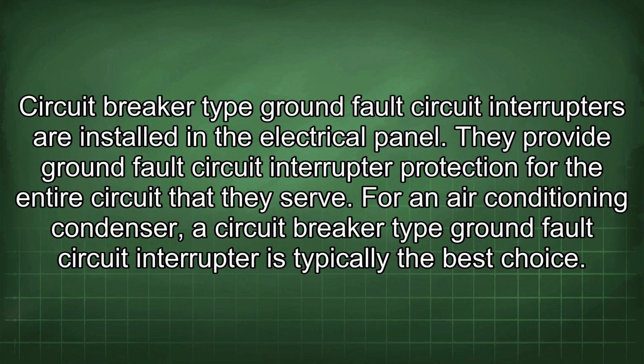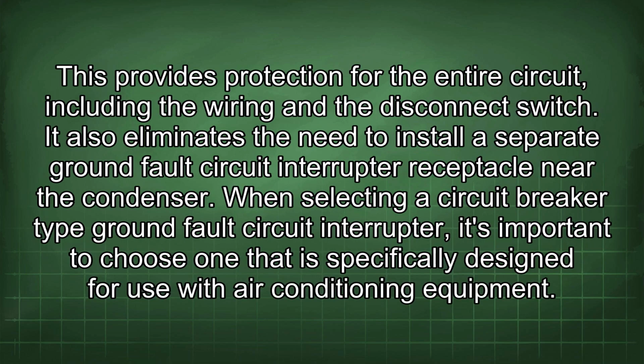For an air conditioning condenser, a circuit breaker type ground fault circuit interrupter is typically the best choice. This provides protection for the entire circuit, including the wiring and the disconnect switch. It also eliminates the need to install a separate ground fault circuit interrupter receptacle near the condenser. When selecting a circuit breaker type ground fault circuit interrupter, it's important to choose one that is specifically designed for use with air conditioning equipment.